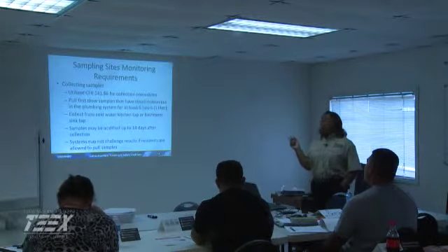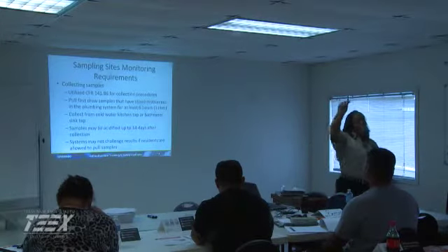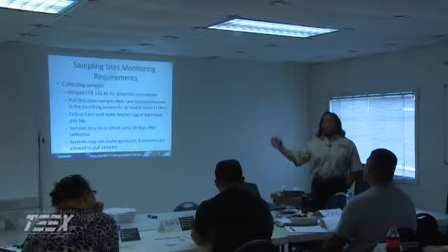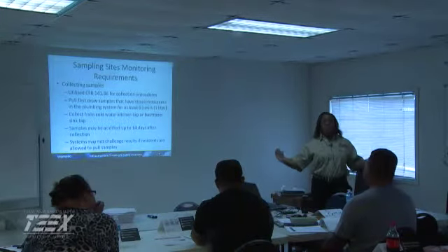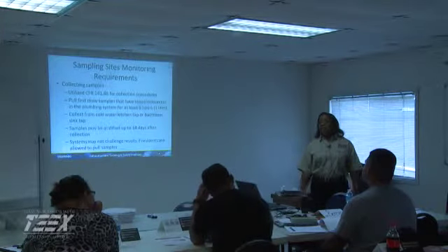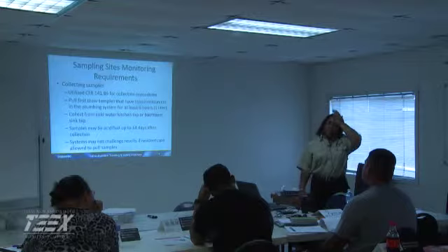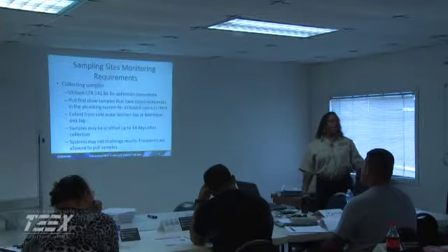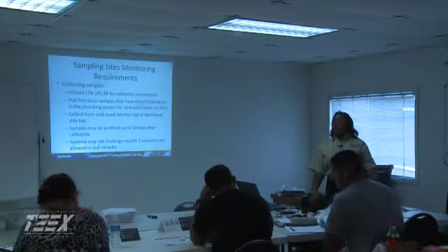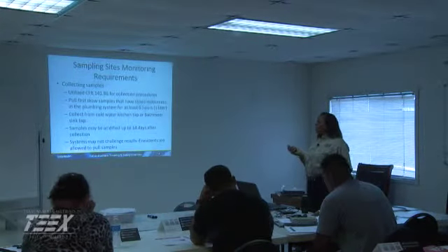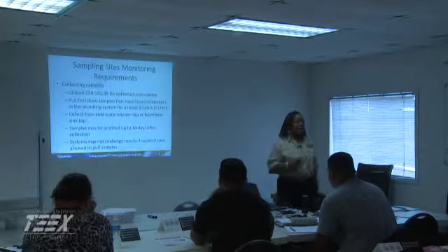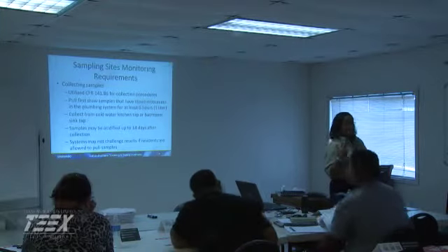Now here's the other thing. You can ask people to pull it the first thing in the morning, or you can ask people to pull it the first thing after work, if the water has been motionless for at least 6 hours. But we can't have homeowners midday remembering, oh, I forgot to pull that sample, let me go pull that sample, and they've cooked breakfast, they've bathed, they've done it all. Collect from the cold water tap. Not hot, but cold. Very important.